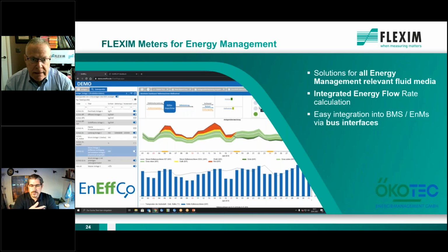As said, we provide solutions for basically all energy management relevant fluid media, and the goal, of course, would be to get all this information into your building management system or a dedicated energy management system. This is an example where you can monitor your chiller to be sure that you are within your efficiency, that you can take measures as soon as you run out of efficiency, and that you always run at the best efficiency and do not waste energy. This is easy to integrate through our bus systems, Modbus, MBus, and so on, so that you can easily get the data out of the meter all at once, flow, energy, temperature information, and draw conclusions from it. And best, of course, with the help of dedicated software.